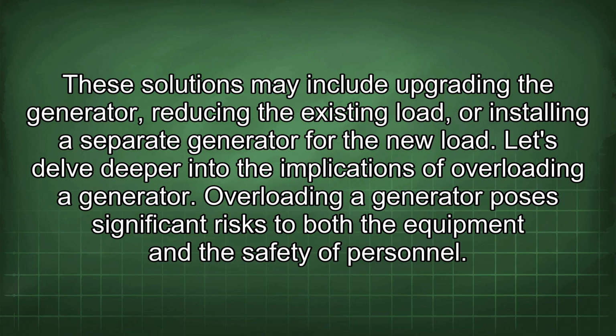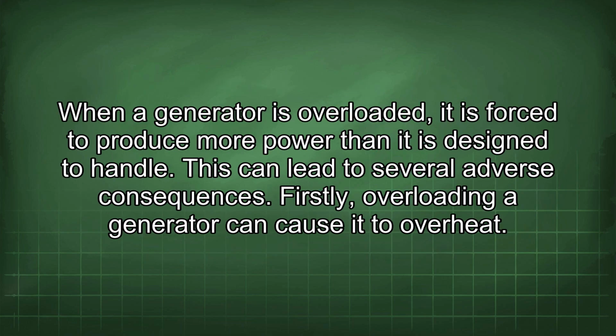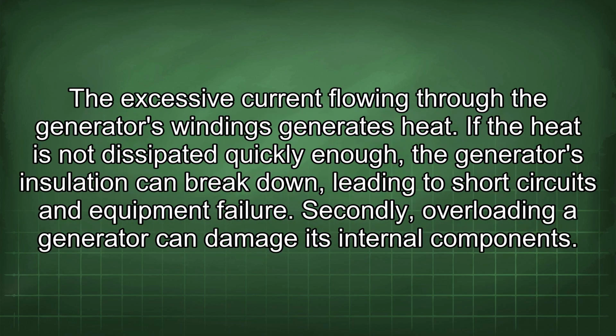Overloading a generator poses significant risks to both the equipment and the safety of personnel. When a generator is overloaded, it is forced to produce more power than it is designed to handle. This can lead to several adverse consequences. Firstly, overloading a generator can cause it to overheat. The excessive current flowing through the generator's windings generates heat. If the heat is not dissipated quickly enough, the generator's insulation can break down, leading to short circuits and equipment failure.